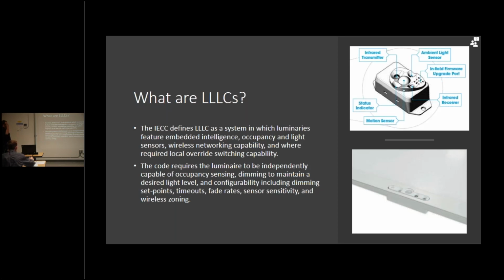So IECC actually has a definition for LLLCs in which luminaires feature an embedded intelligence, occupancy and light sensors, wireless networking capability, and where required local override switching capacity. The code requires the luminaire to be independently capable of occupancy sensing, dimming, to maintain a desired light level, including configurability to dim, set points for stepping, if necessary, timeouts, sensor sensitivity, and wireless zoning.